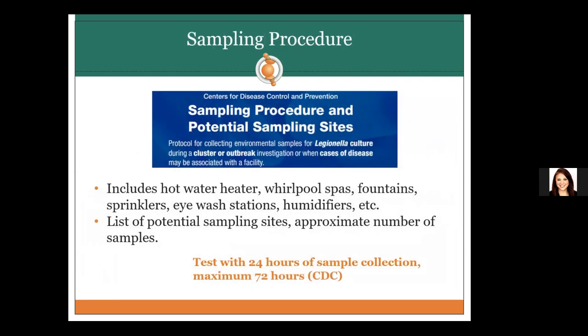Sampling procedures cover hot water areas, whirlpool areas, fountains, sprinklers — basically anywhere water can escape and become aerosolized is a good area for sampling. Ideally, samples should be tested within 24 hours of collection, but the CDC allows up to 72 hours. This is because Legionella free-flowing in water can potentially die off over time, leading to false negatives.